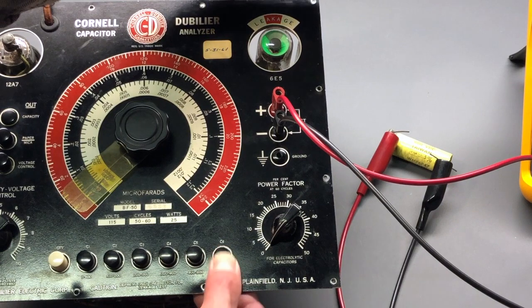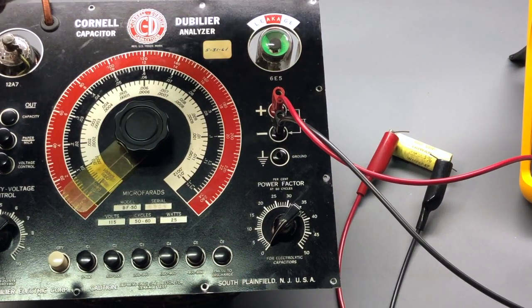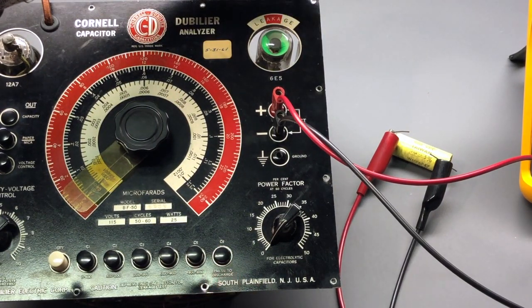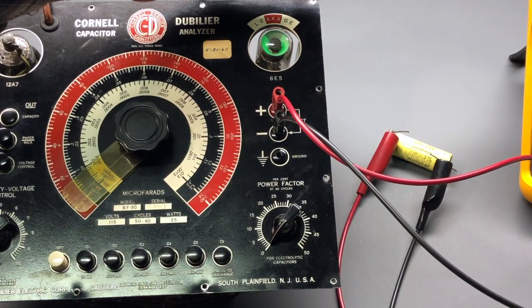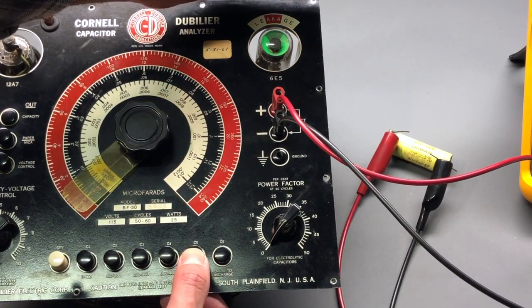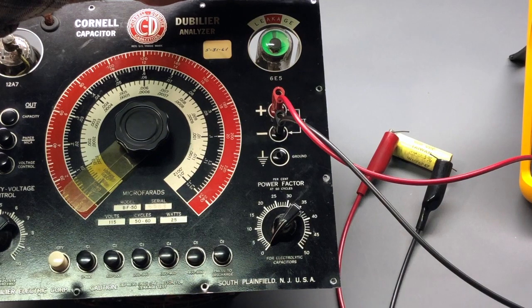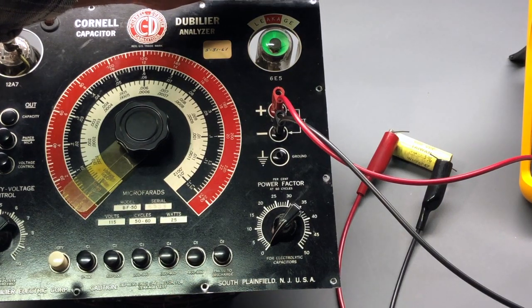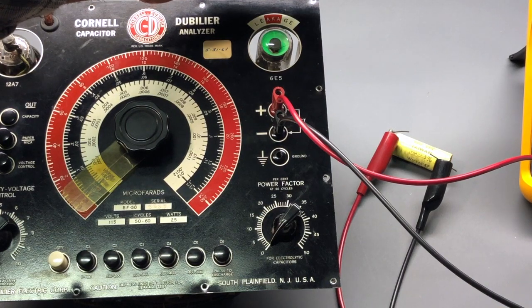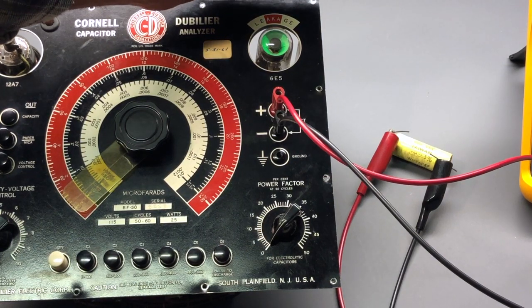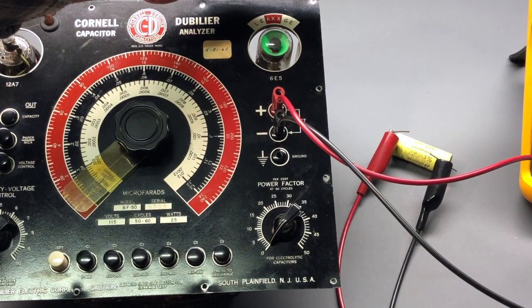But running the test one more time. Again, this is the press to discharge. Discharges the capacitor. You can see the eye tube close down, which would indicate current flowing into that capacitor since we just discharged it. And now you can see the eye tube opening. It's a very wide opening segment or wedge shape, which is very good.